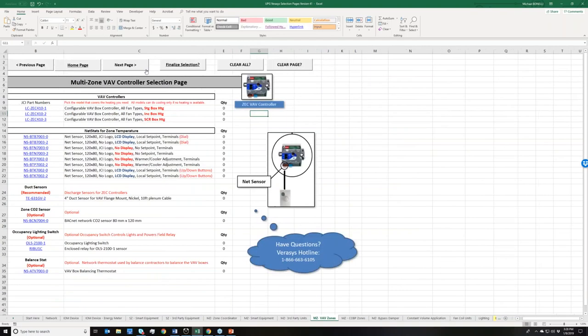The first thing that we go to is VAVs, so these are our VAV controllers. Right now we have three different VAV controllers with Verasys. We can support up to either stage box heat, incremental box heat, or SCR box heat. Right now you have to make sure that you select the right one depending on the box heat that's going to be present on the job. In the future, we're actually going to have one controller that replaces all three of these.